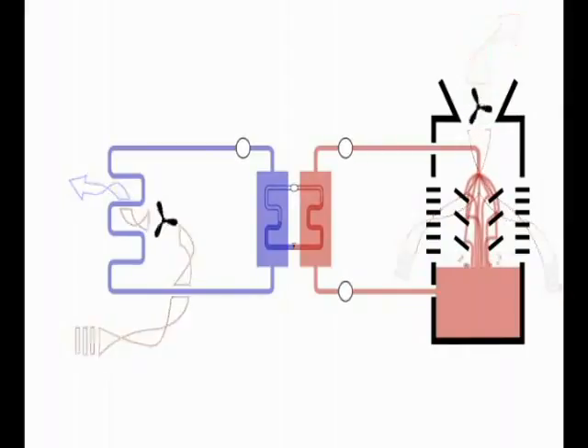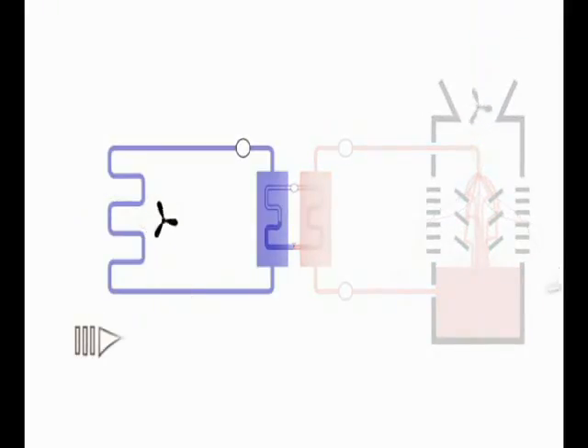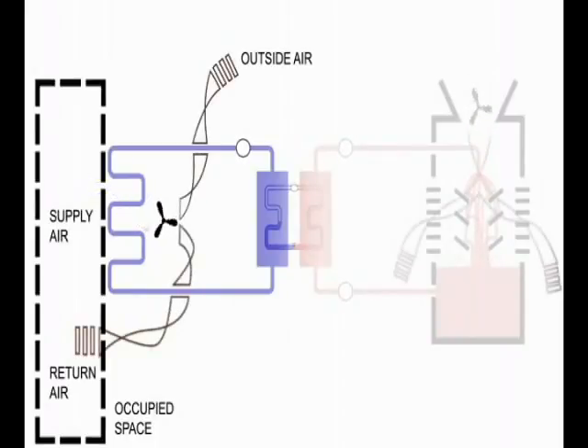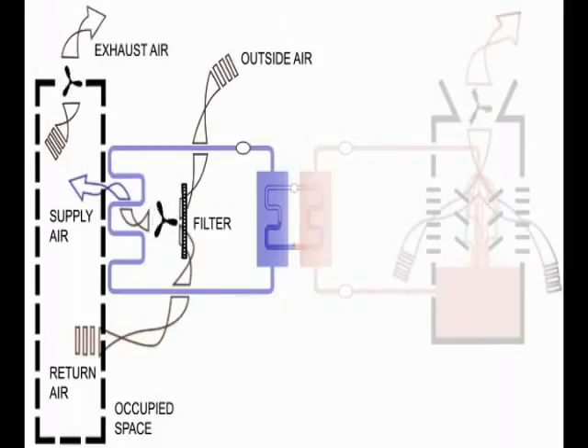As we've seen, the recirculated air is cooled by the chilled water coil in the air handling unit, but that's a bit of a lazy simplification. In fact, we will use the air handling unit not only as a thermal comfort device, but also an indoor air quality device. Outside air is introduced into the air loop, and that outside air combines with recirculated air from the room before both volumes of air move across a filter. Of course, simply adding lots of outside air without exhausting some of the inside air is not stable. So exhaust fans release some of the portion of the stale interior air, that portion not destined for recirculation, to the outdoors.